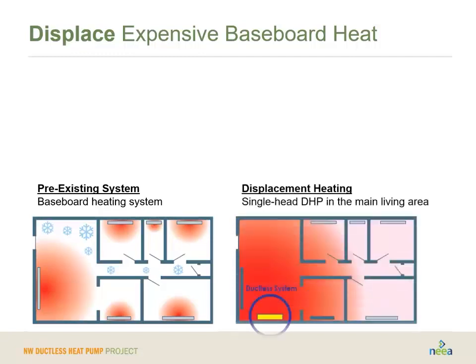So displacing this type of system means that we put a ductless heat pump in the main body of the house, and we allow it to do the heating and cooling in that main area. Again, typically the living room, dining room, family room, kitchen, and major part of the hallway. That's a displacement system. We've displaced at least that large baseboard or a couple of large baseboards in the main body, and maybe even that closest bedroom, particularly if homeowners keep the bedroom doors open. When we think about this, we usually think about displacing anywhere from 30 to 70% of the need to heat in the home. It also provides summer air conditioning in that area.